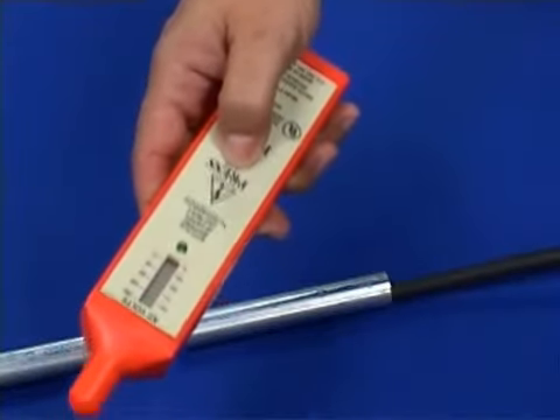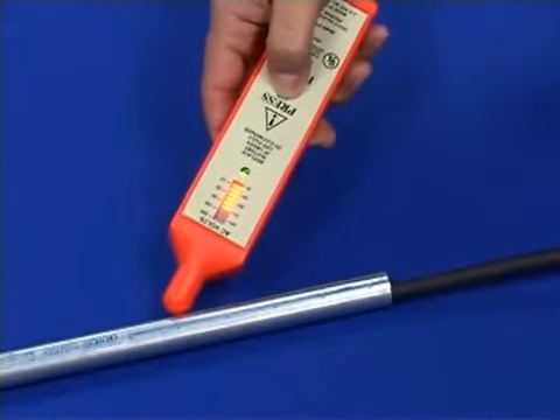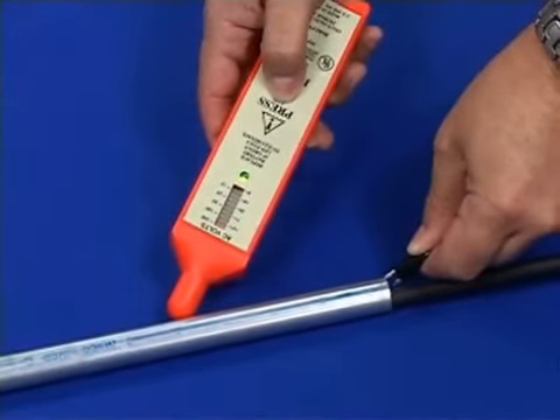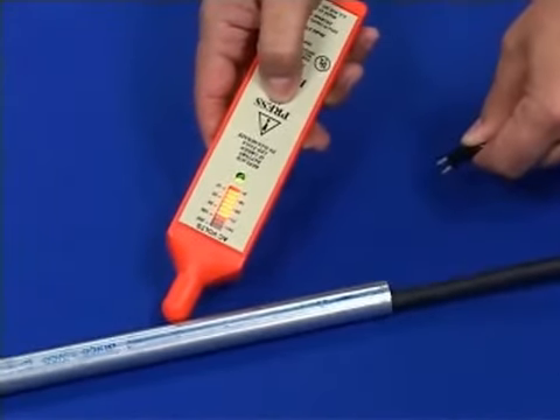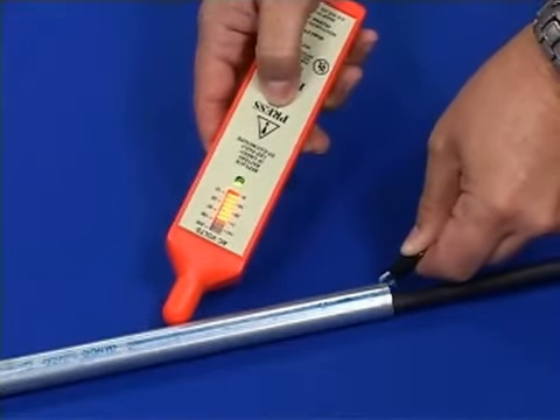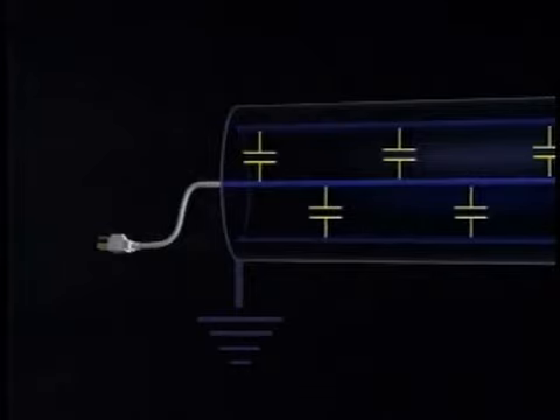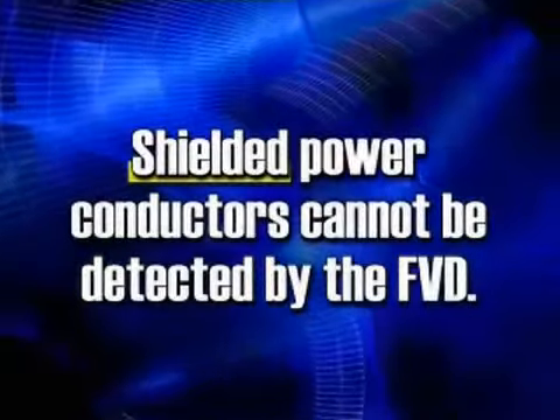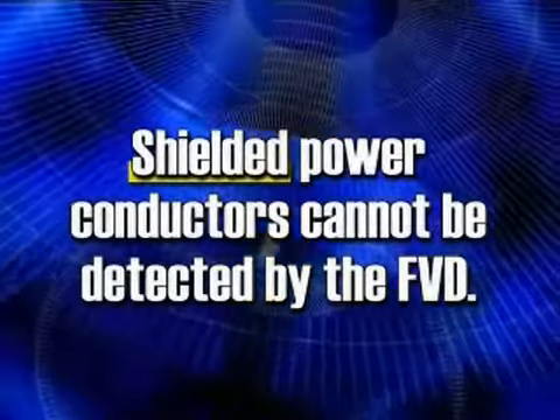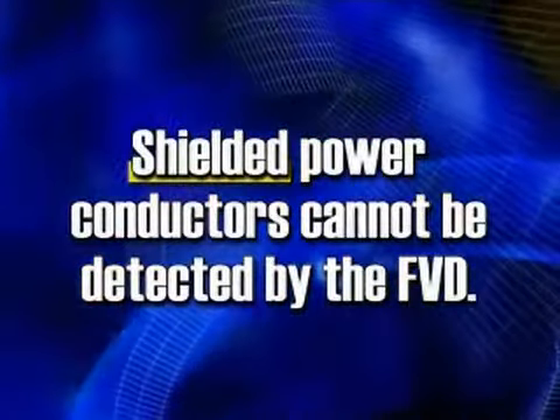When we test this conduit with the FVD, it appears to be energized. Now, watch what happens when the conduit is grounded. Note that no power is detected. In this case, the conduit was energized by the power inside until it was grounded. This energy was coupled to the conduit through the capacitance between the conduit and the power conductors. As you saw, the grounded conduit effectively shielded the power from being detected. It is important to understand that shielded power conductors cannot be detected by the FVD.